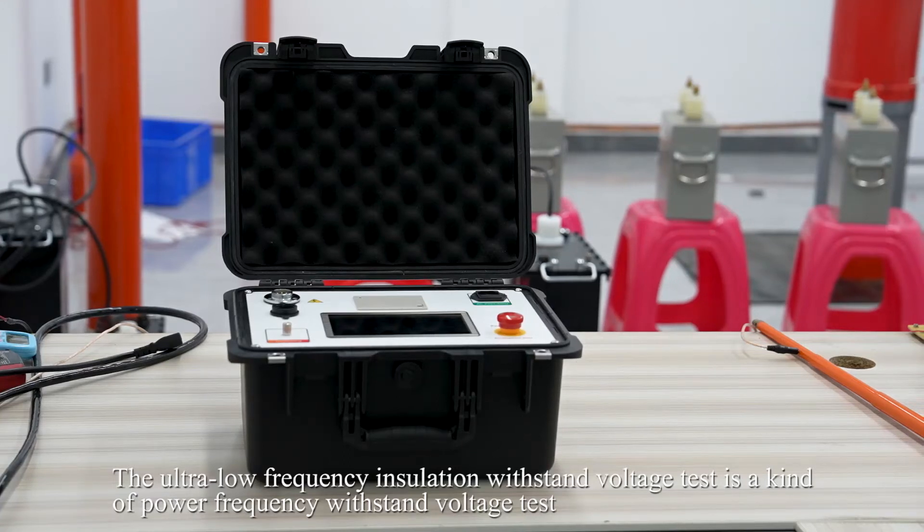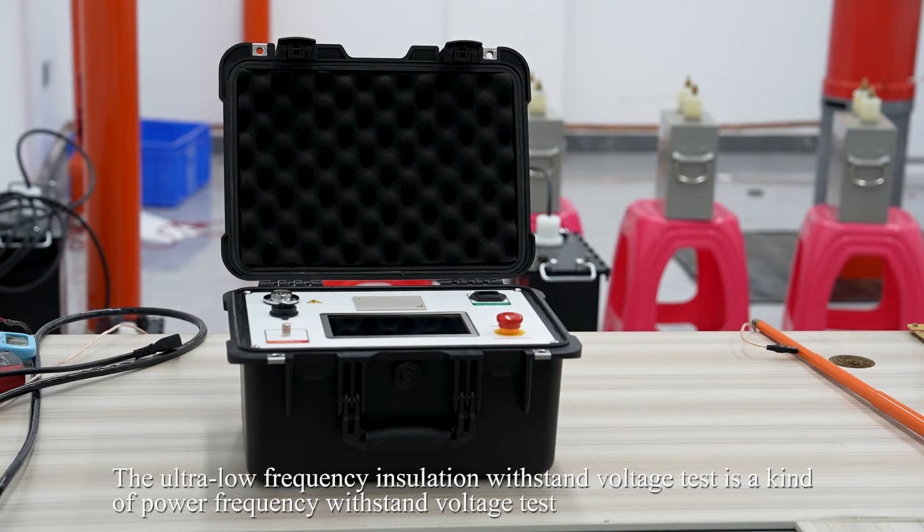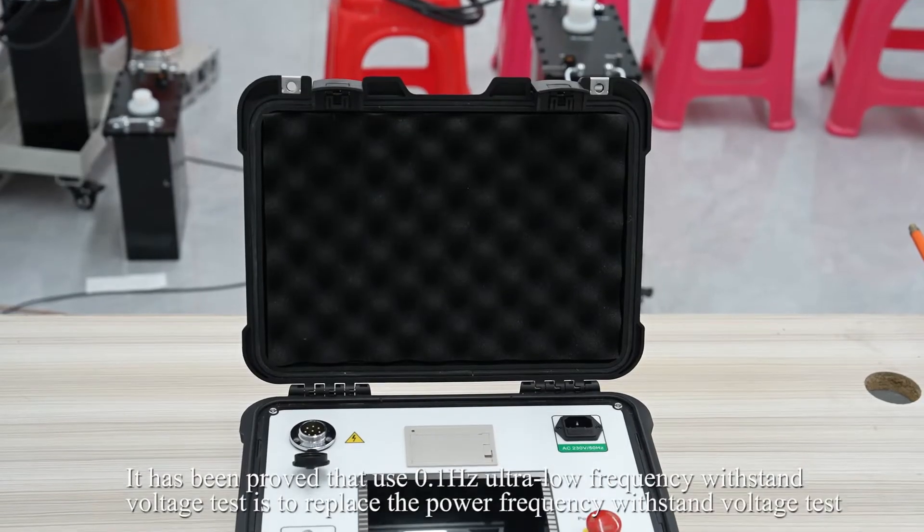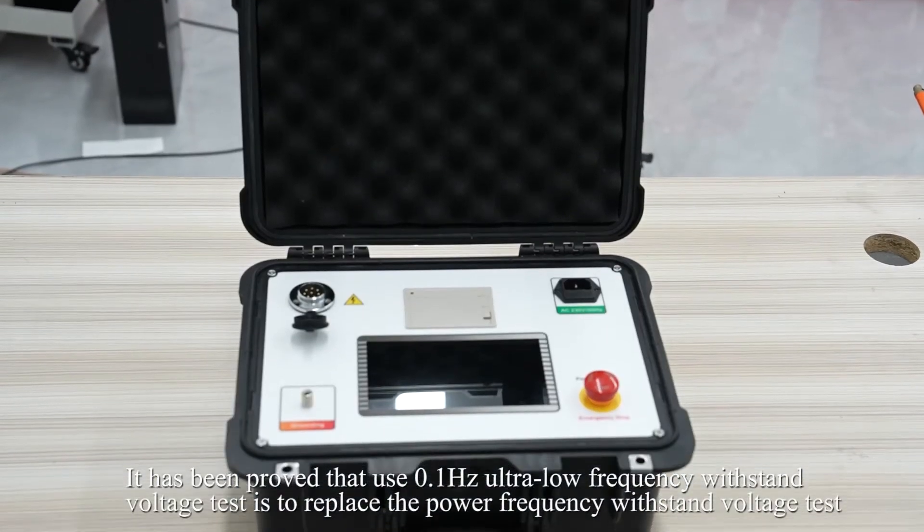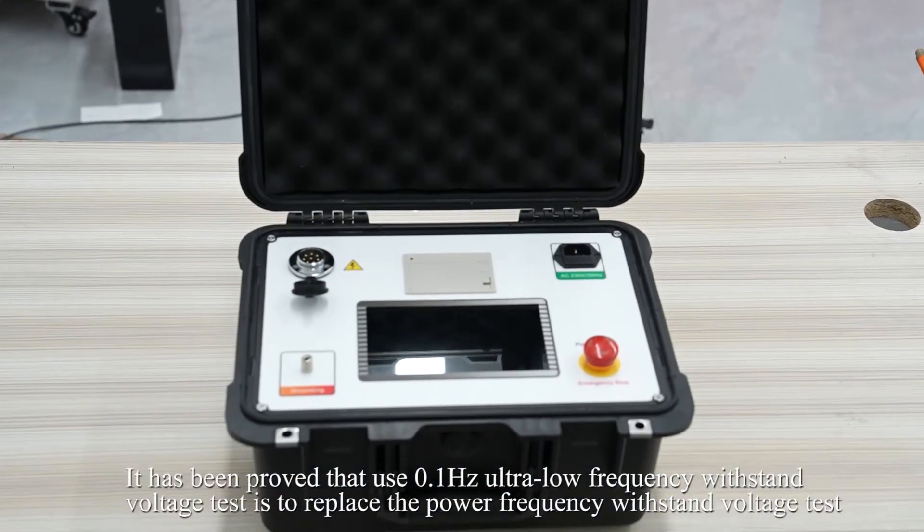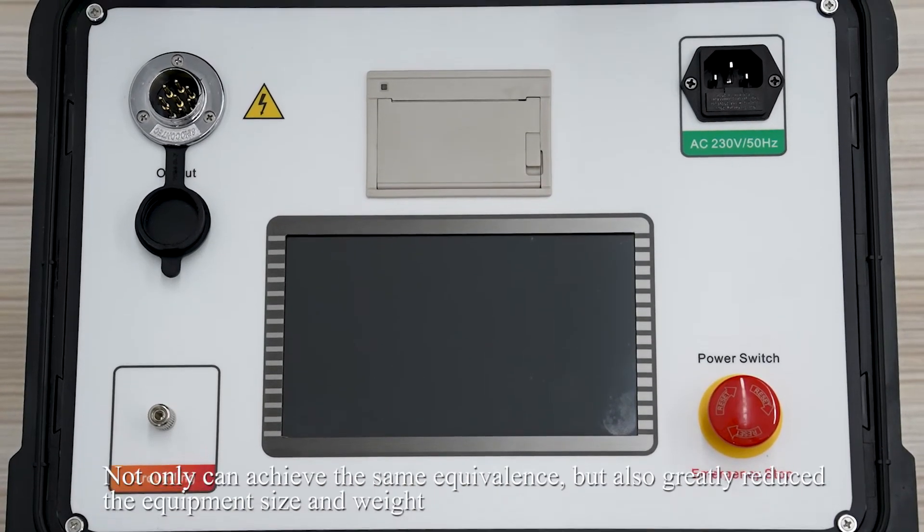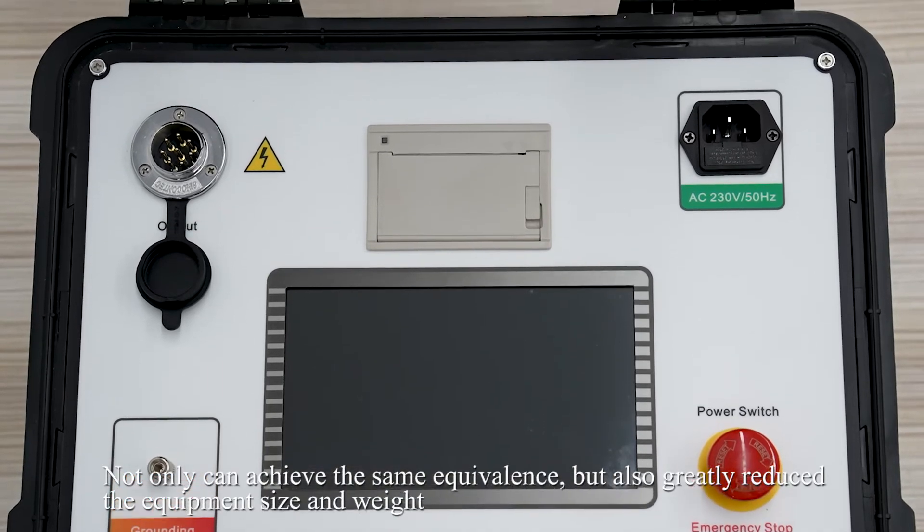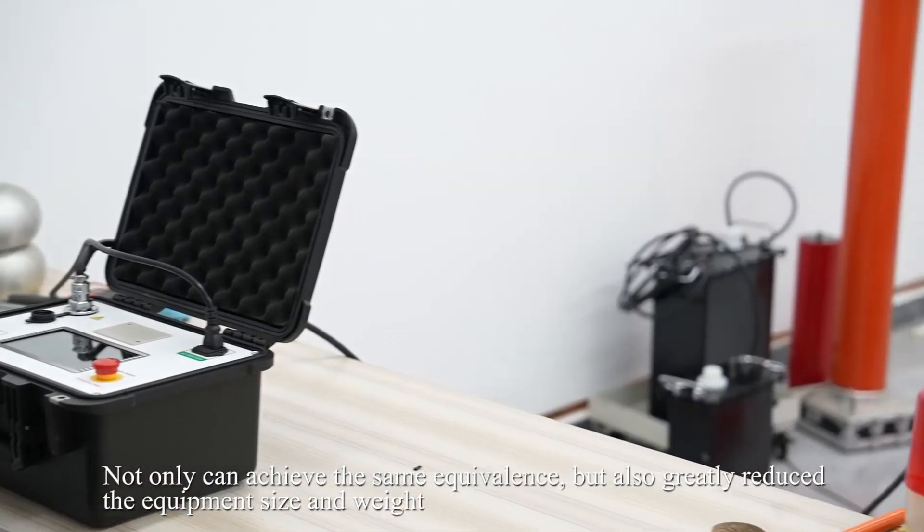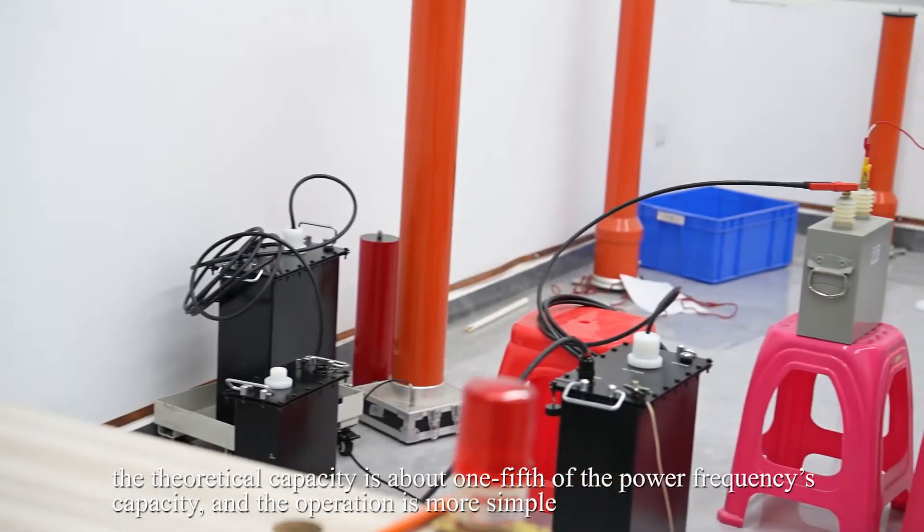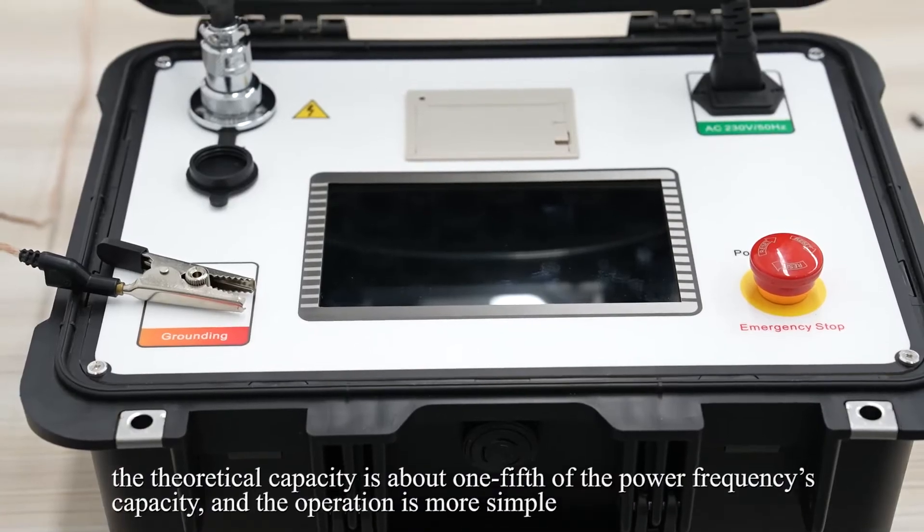The ultra-low-frequency insulation withstand voltage test is a kind of power-frequency withstand voltage test. It has been proved that using 0.1 Hz ultra-low-frequency can replace the power-frequency test, achieving the same equivalence while greatly reducing equipment size and weight. The theoretical capacity is about one-fifth of the power-frequency capacity, and the operation is more simple.